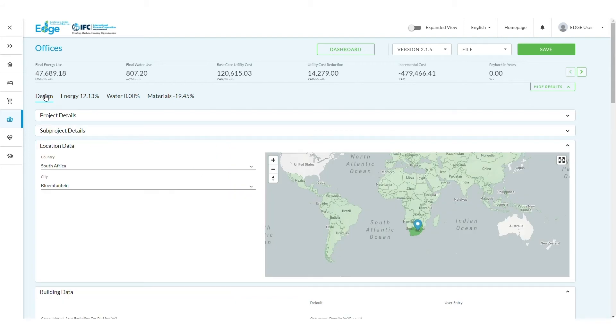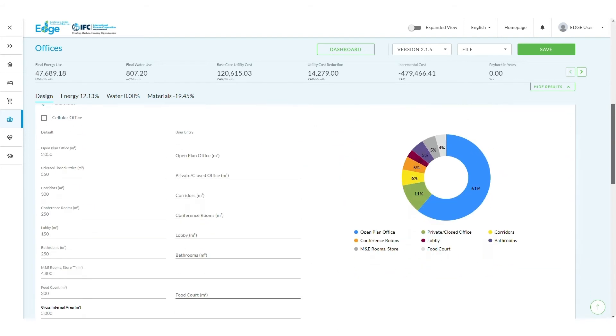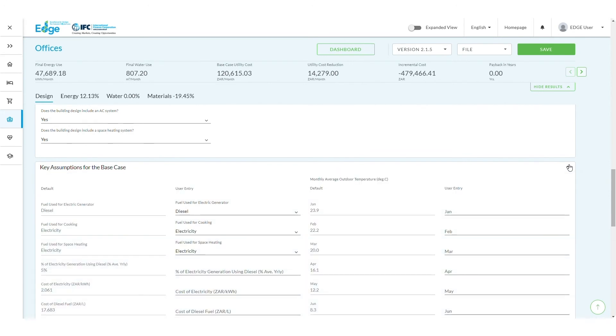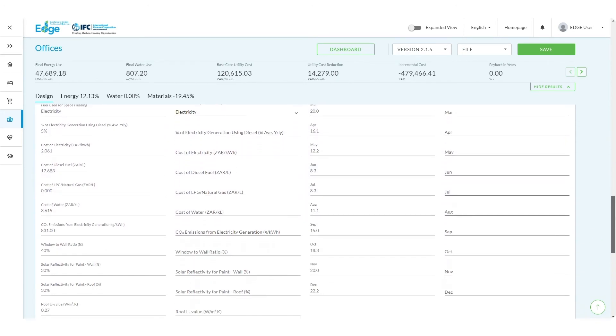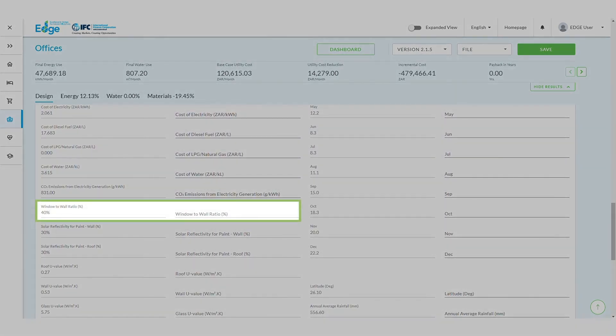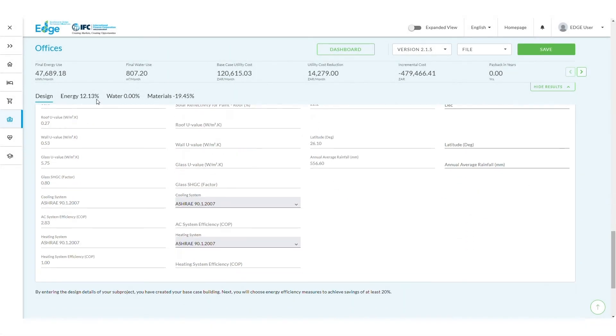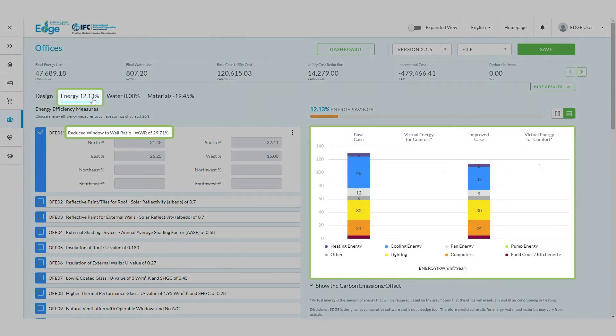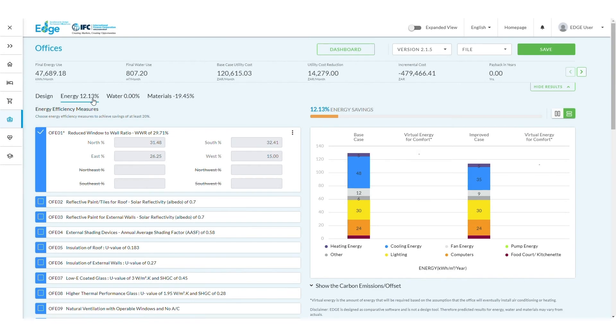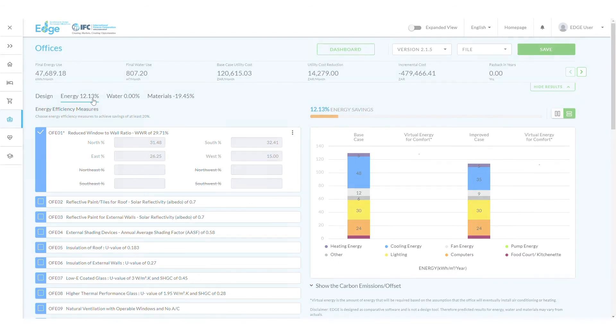EDGE will compare the performance of a project's WWR to the local base case. The base case WWR can be found in the Key Assumptions section of the Design tab. Typically, a lower WWR results in energy savings. When the WWR is higher than the base case as indicated in the Key Assumptions, a project will typically have negative savings. The higher WWR will have to be compensated for by other energy-saving measures.